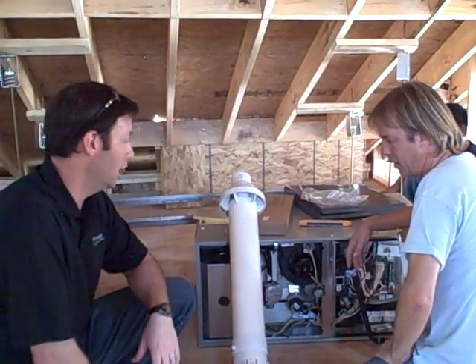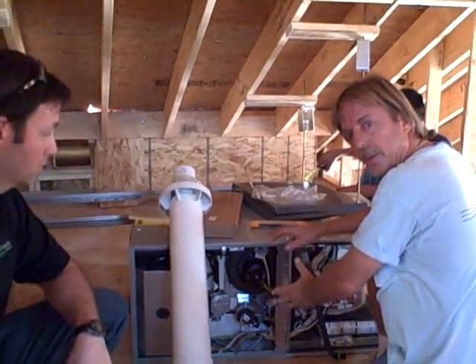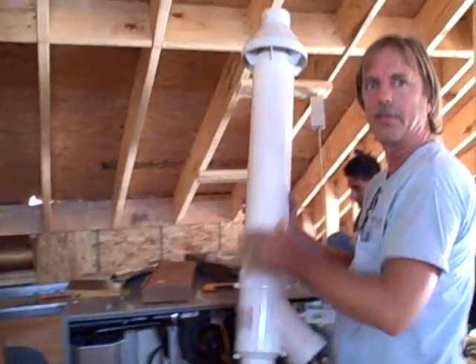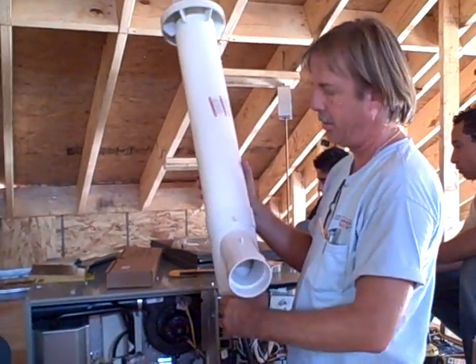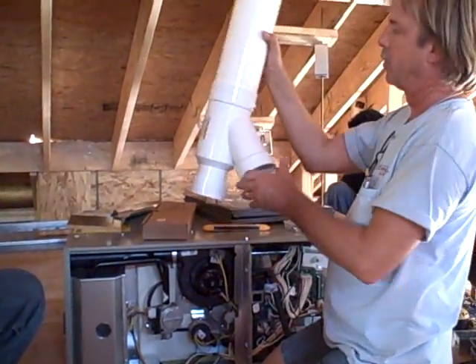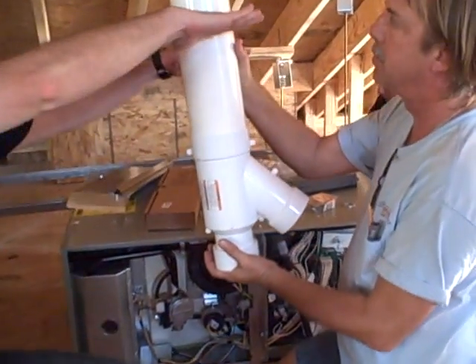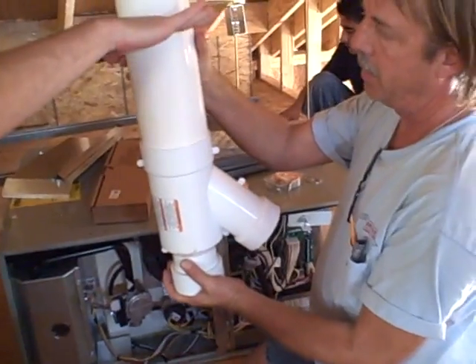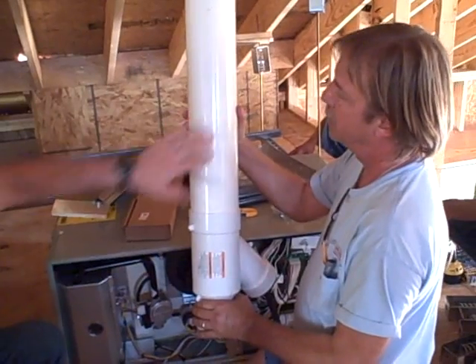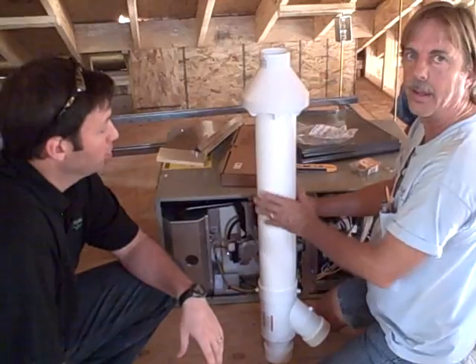What's one of the ways that we get to that higher efficiency level with this unit, Bert? Well for one it has two heat exchangers in it to remove more heat. And it's so efficient that you're able to run it through plastic versus the normal metal. So when it's all a sealed chamber — we bring in fresh air through here and exhaust it through here. And because it's so efficient, it can actually vent those hot gases through that plastic because those gases are much, much cooler than on a standard unit.